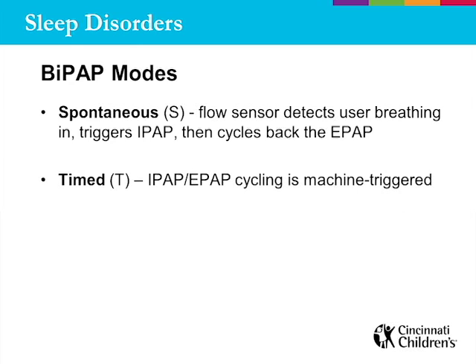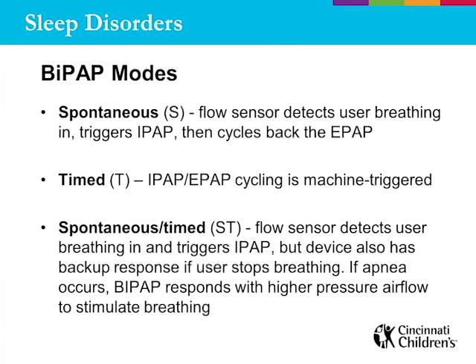Timed is when the IPAP and EPAP cycling is machine triggered. Spontaneous timed is when the flow sensor detects the user breathing in and triggers the IPAP, but the device also has a backup response if the user stops breathing.